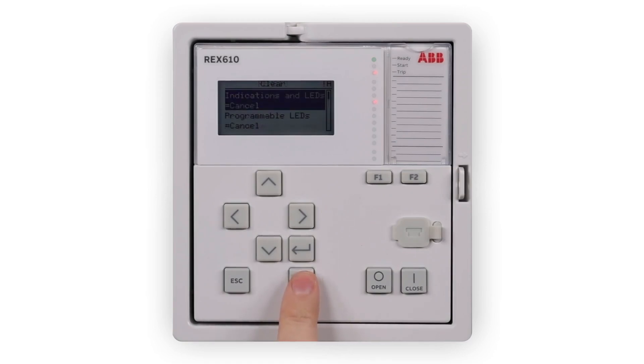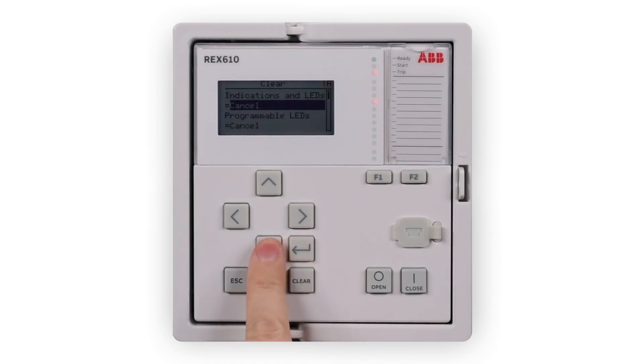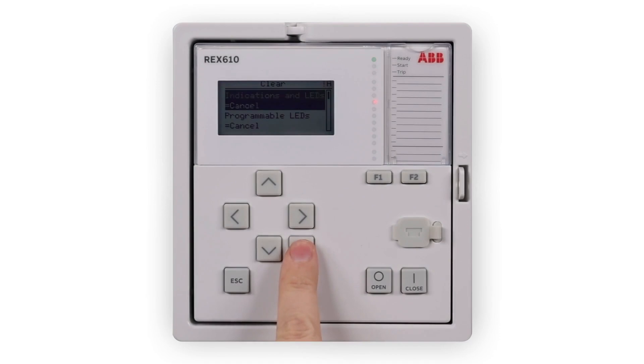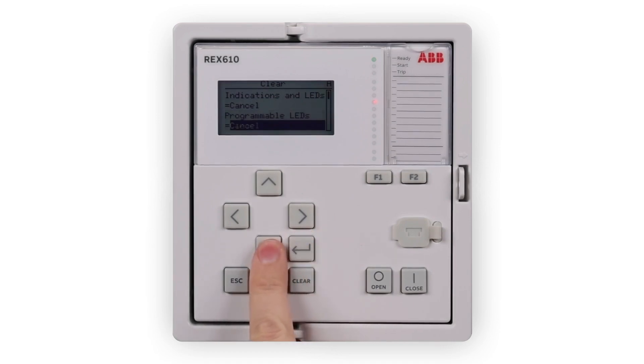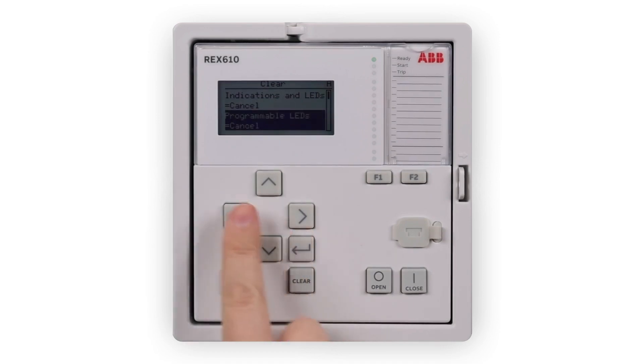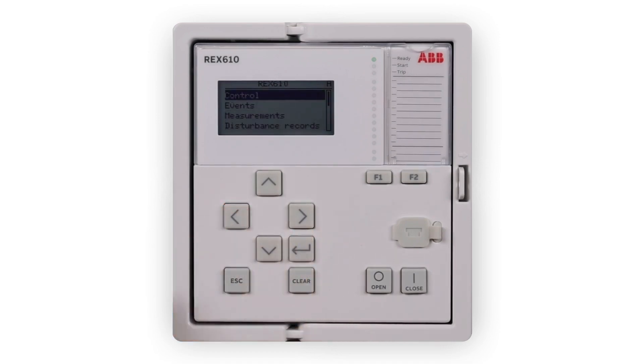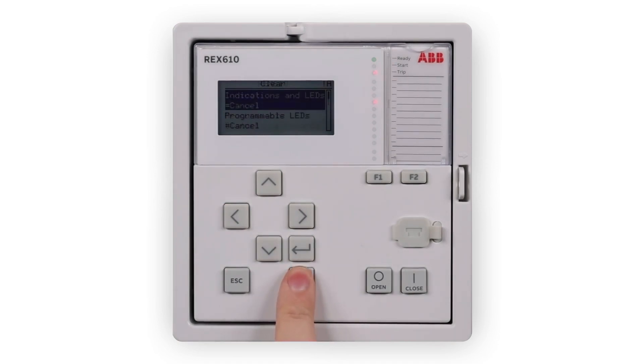With appropriate user rights, the clear button is for activating the clear reset view where the user may individually select what to clear. Alternatively, the clear button can be pressed for 6 seconds to clear the programmable LEDs. A 3 second press clears the trip LEDs.